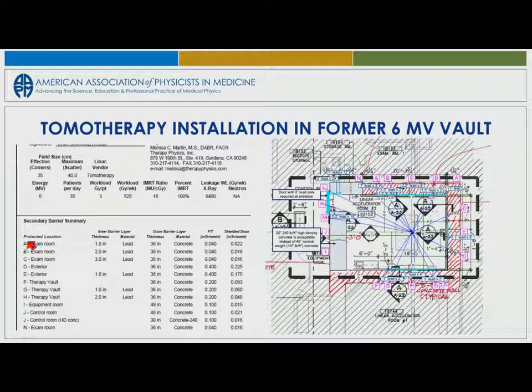And this is what, for Tomo, shows all the different points of calculation. You had to do every one of these and show that every individual point was actually shielded, so that the shielded dose rate is less than the permitted rate.